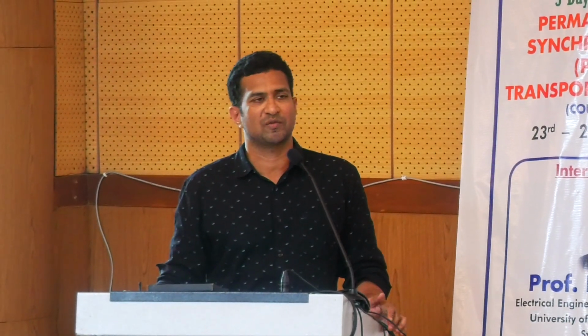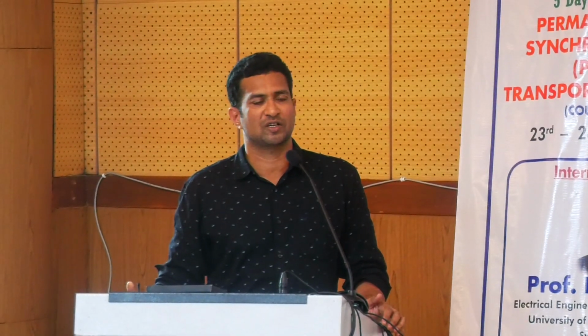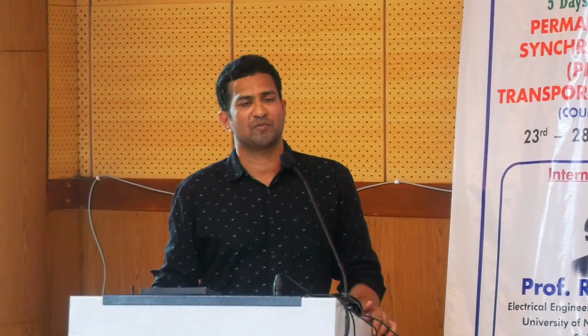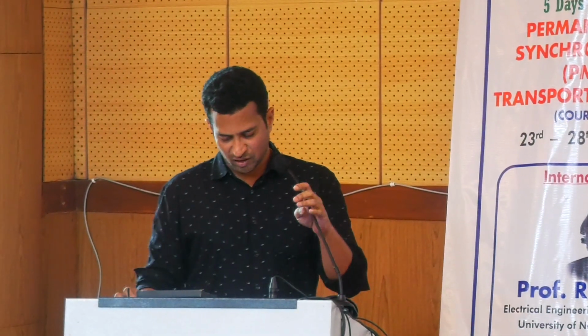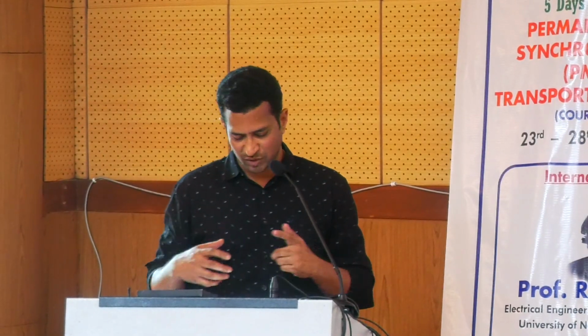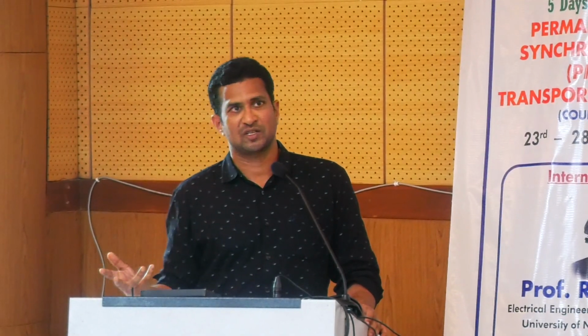We will usually operate this converter in two modes of operation. Depending on your application, it may operate in the voltage control mode or the current control mode. The meaning is that the inverter will operate as a controlled voltage source, or as a controlled current source. Next, we need to control the current and voltage inside the converter, to cope with variations in the DC input voltage. That means irrespective of the DC input voltage, we are supposed to regulate the output voltage on the other side.